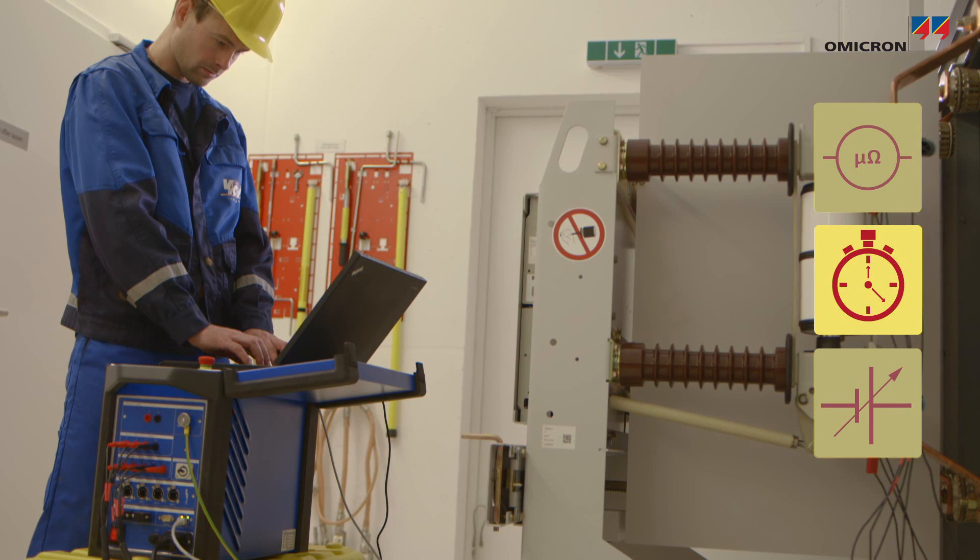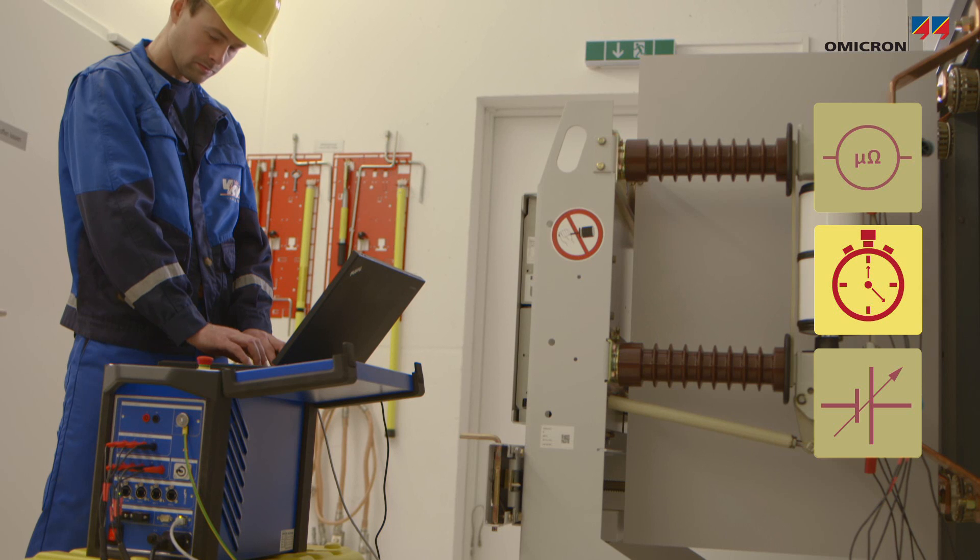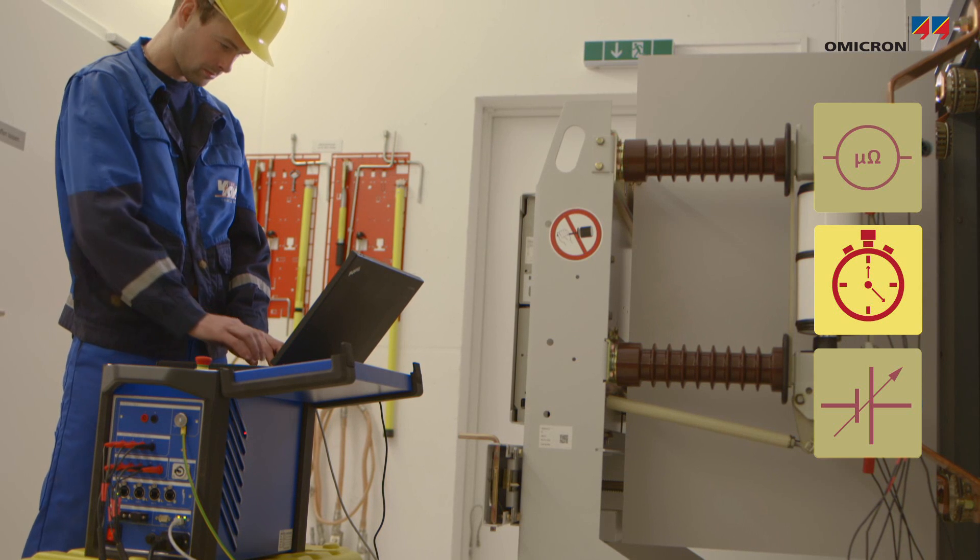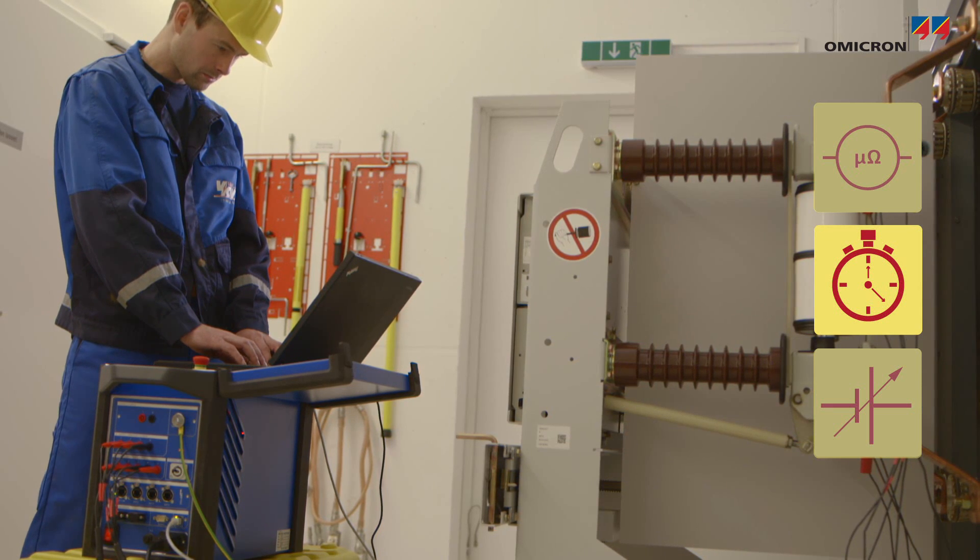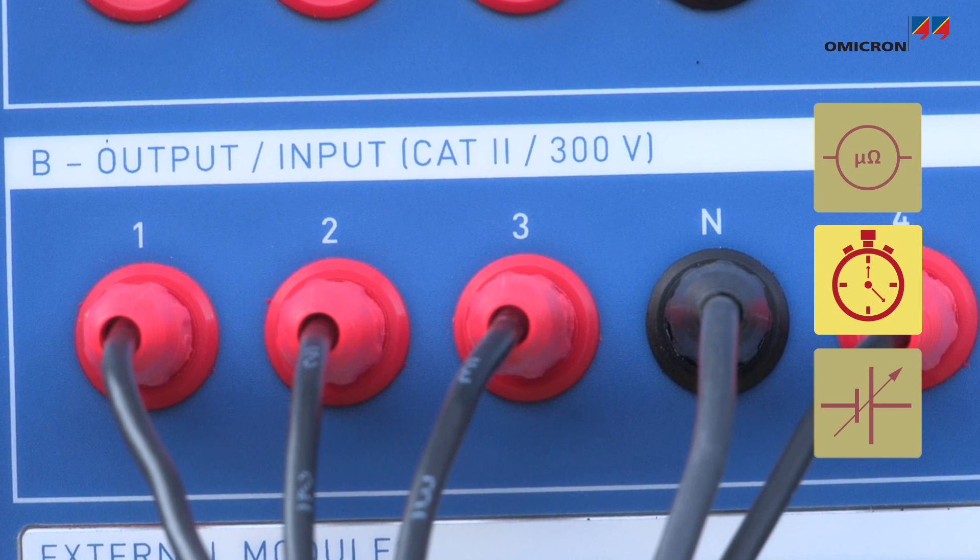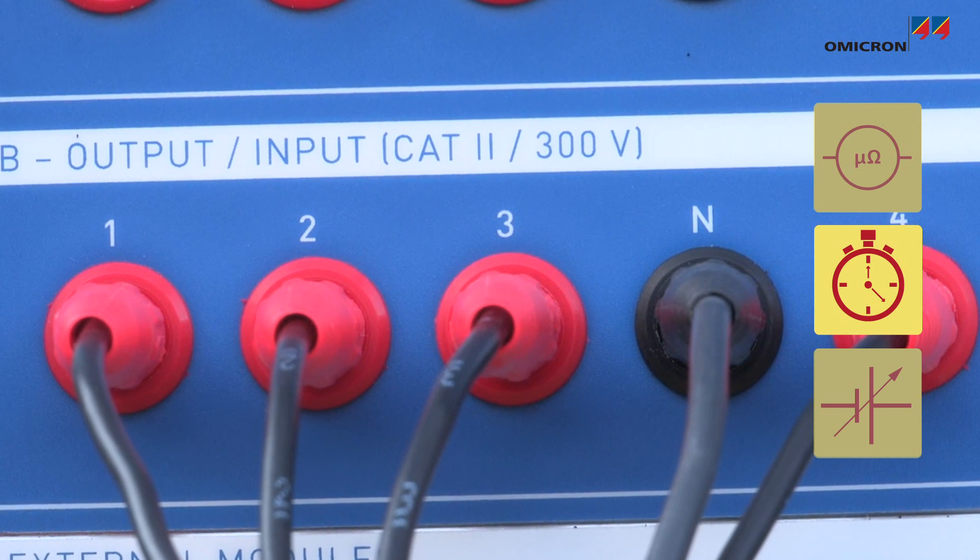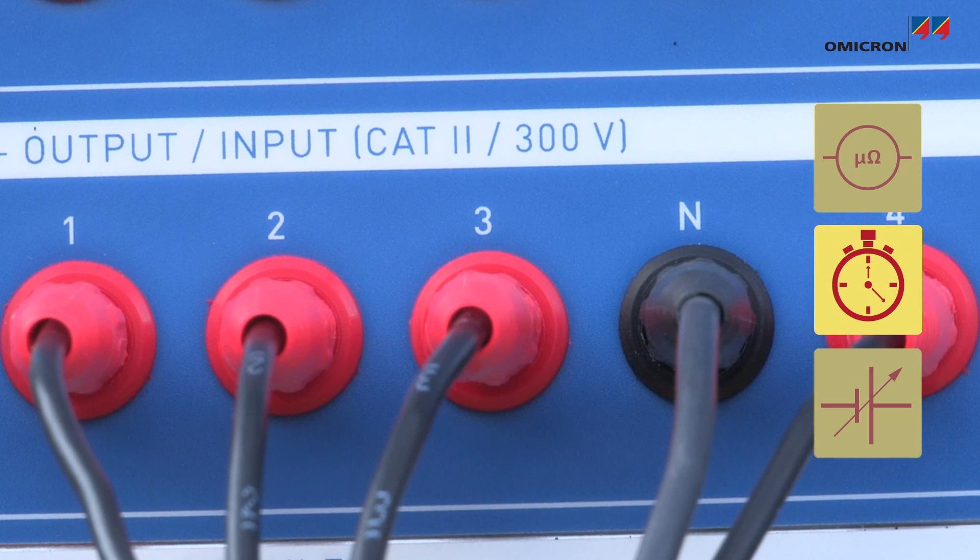When measuring the opening and closing times of main and auxiliary contacts, as well as the deviations between them, the CIBANO can operate the trip and closing coils and automatically record the voltage and current signals in order to perform a comprehensive analysis.